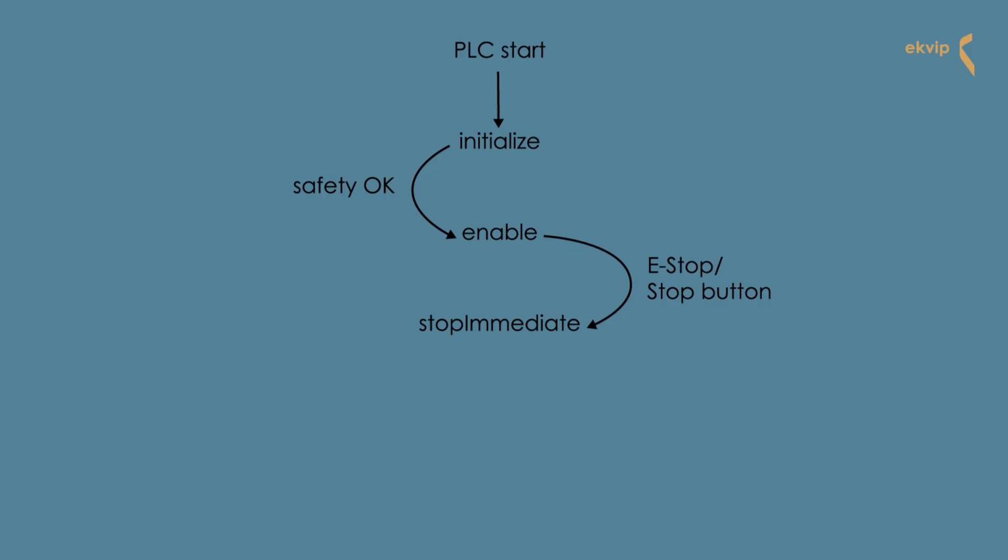The stop method should stop axes, cylinders, processes continuously until manual mode is stopped via stop request or immediate stop. This method is called automatically by the operation mode handler before disabling the machine or if the operator selects an immediate stop. Attention! If this method returns the state error, the operation mode handler automatically disables the entire machine.